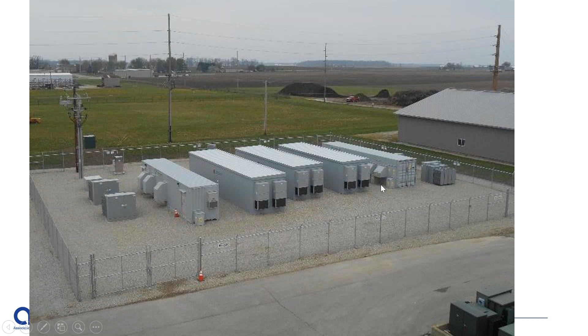One of the requirements within Article 706 is the ability to do a disconnect. You have to be able to disconnect all of the ungrounded conductors coming from the energy storage system, and it has to be readily accessible and in sight of the energy storage system. The point is that if you have to do maintenance, or have some type of issue with that system, you want to be able to disconnect it from the building load and from any other connection.